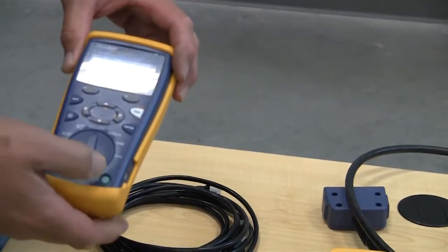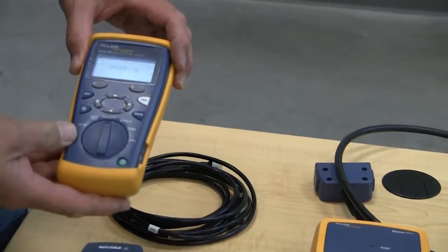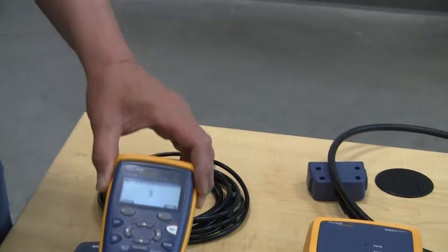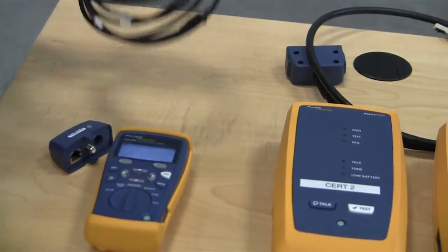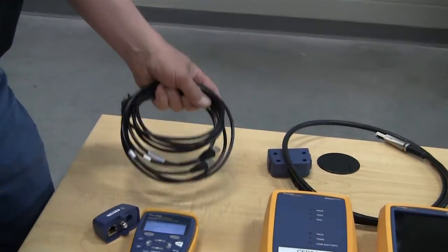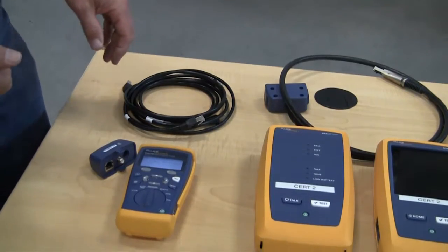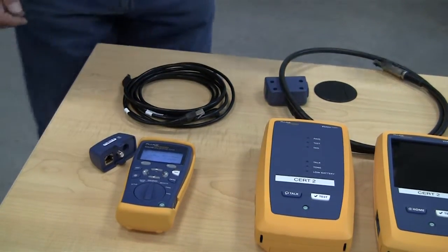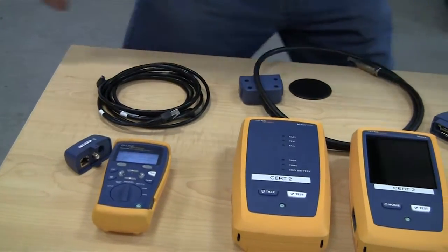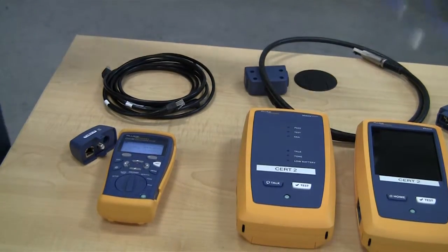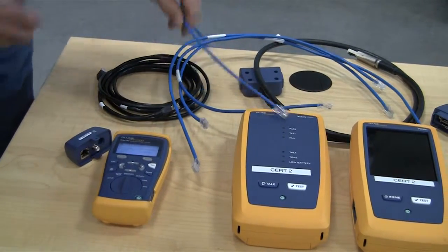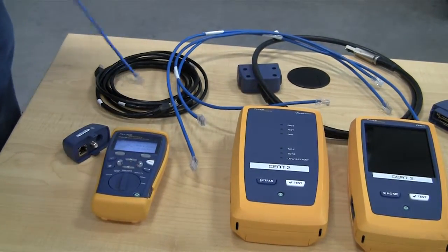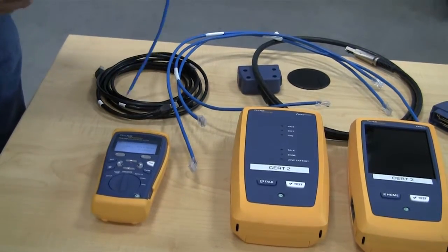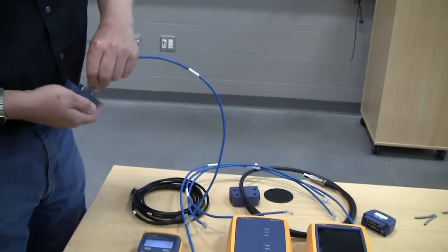First we'll turn on the qualifier. It comes with two test set cables for use in the field, but we'll take a couple of bad cables and test those so you can see what the different fault scenarios look like. The first one I'll show you is an open cable.